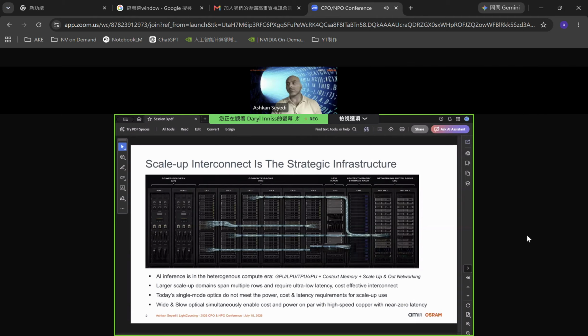That's the point. And somewhere around 60 to 70% of the interconnects that are used in a data center are within a row themselves. And especially as inference workloads and the models get to be bigger, the scale up domain definitely has a lot of benefit. There is a better performance per watt improvement on either token throughput or number of users served. And because the row is quite busy and quite dense of the different kinds of racks you have to bring in, as well as the infrastructure of power and cooling, these larger scale up domains will have to span multiple rows, 2 rows, 3, 4 rows, kind of like that. So there's a very sweet spot of the radius of around 100 to maybe 125 meters where a significant amount of interconnectivity has to happen in a data center.